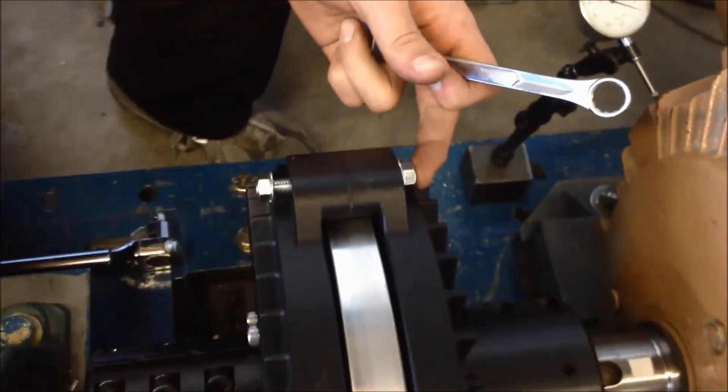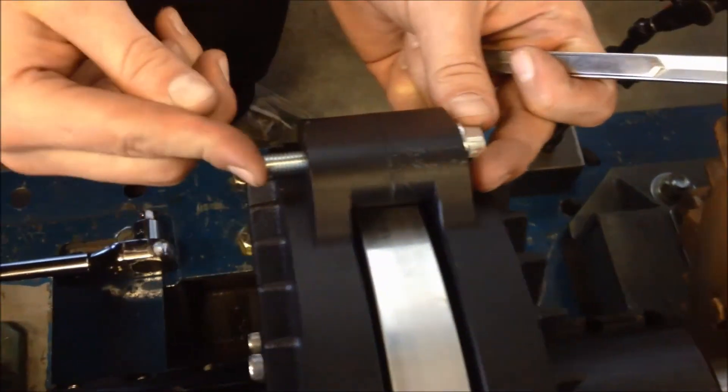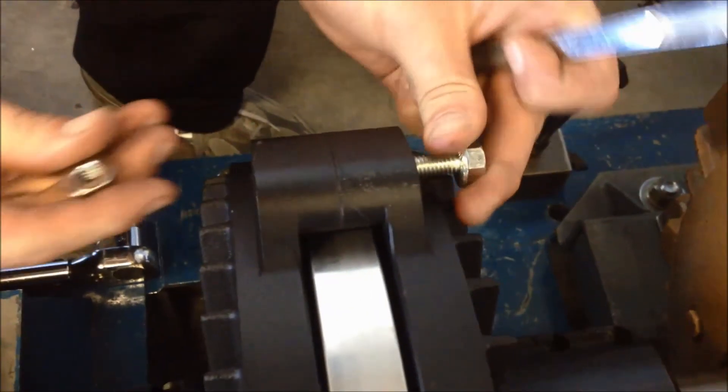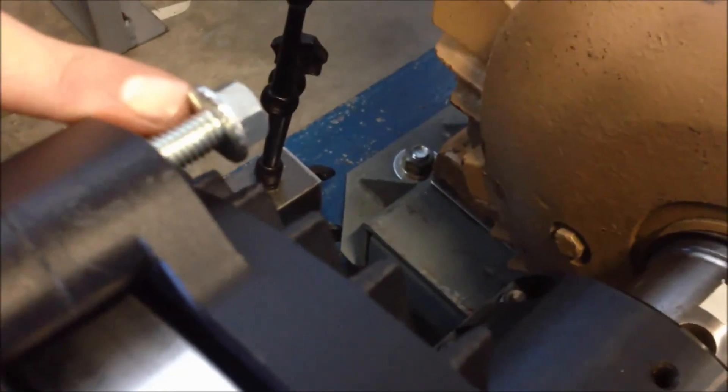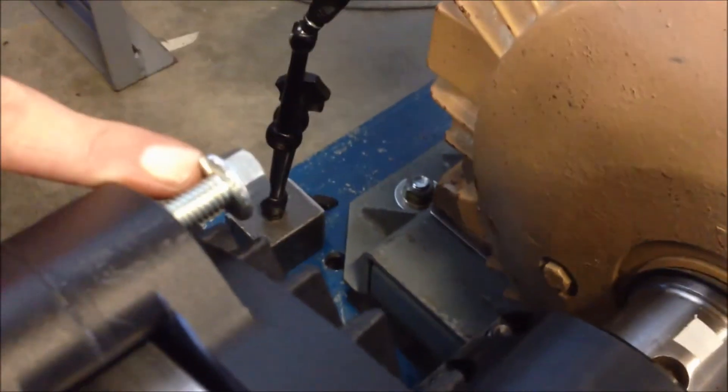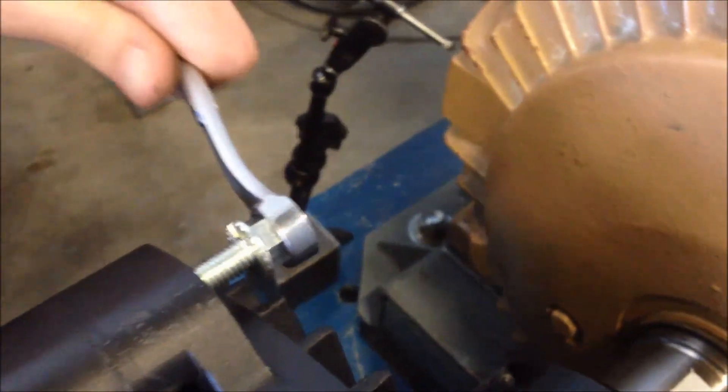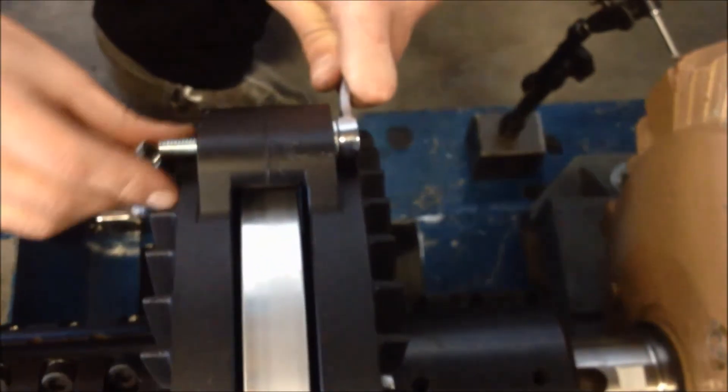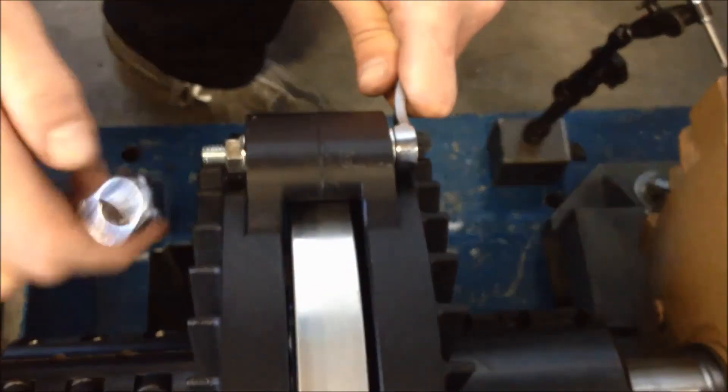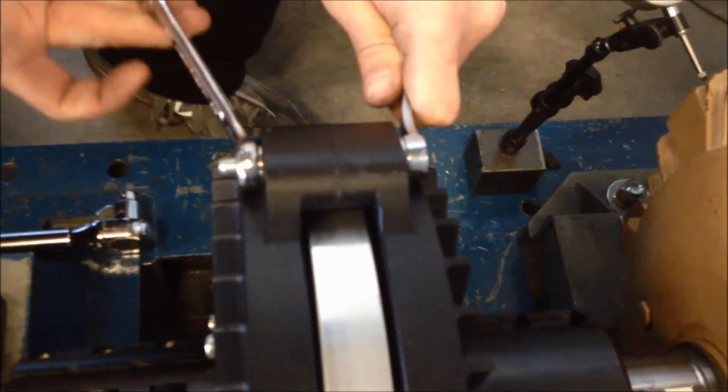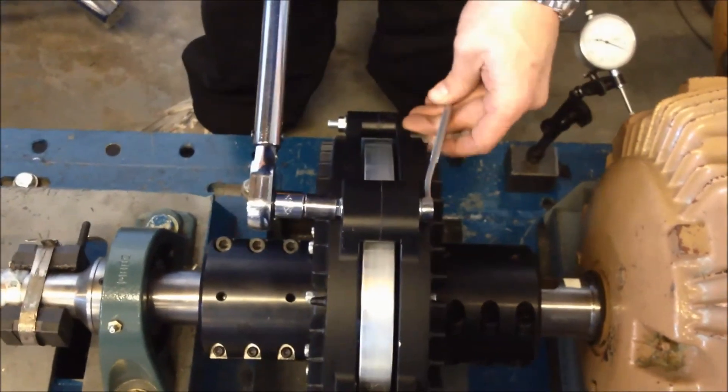Verify that the six induction rotor spacer bolts are tight. The nut has a smooth face and the bolt has a serrated face. When tightening or loosening this fastener, hold the bolt firm and keep it from rotating and apply torque to the nut. This will allow the bolt head to bite into the aluminum surface locking it in place. Torque the nut to the specified torque outlined in the instruction guide supplied with the FSC coupling.